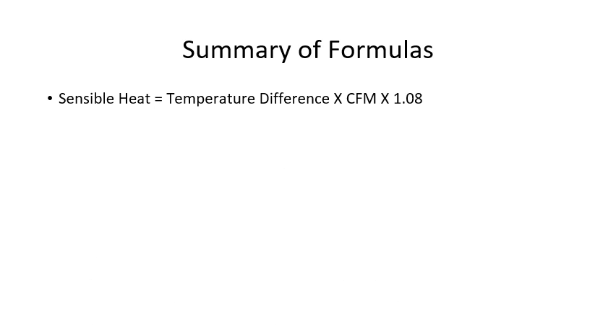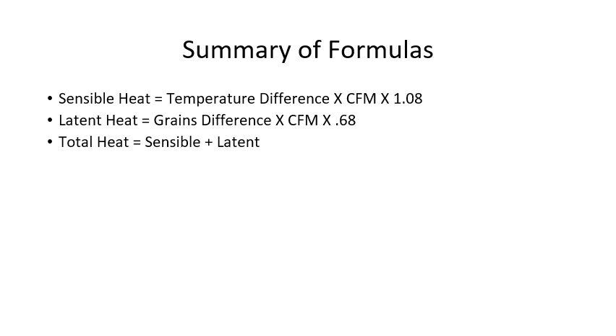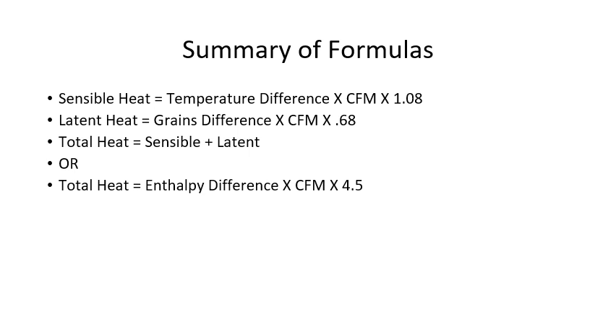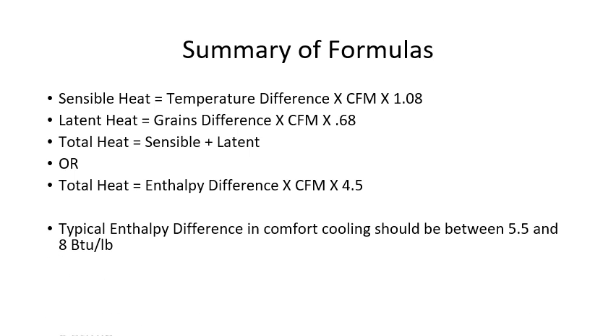Let's take a moment to summarize our formulas — this is a good time to write these down. Our sensible heat formula is temperature difference times CFM times 1.08. Latent heat is grains difference times CFM times 0.68. Total heat can be calculated by adding sensible plus latent, or by using the total heat formula: enthalpy difference times CFM times 4.5. Our typical enthalpy difference in comfort cooling is between 5.5 and 8.0 BTUs per pound. The sensible heat ratio is determined by dividing sensible by total heat, and a typical sensible heat ratio should be between 0.7 and 0.8.